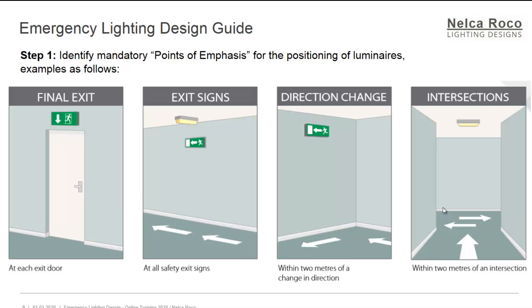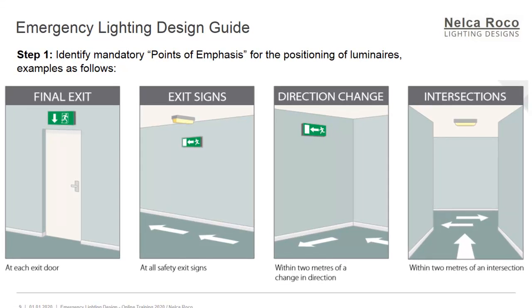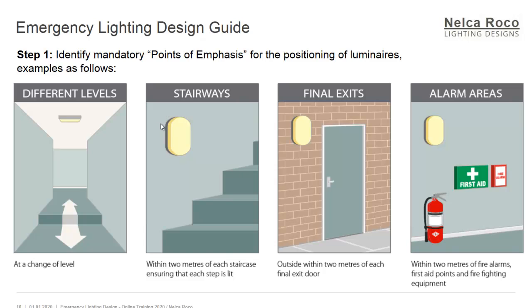Also part of Step 1 are different levels — if there is a change in the steps or the floor levels, you need to add a luminaire pointing to that area. For stairways, this is very important because most of the time people are directly going to the fire exit stairs, so the stairway should have emergency luminaires.